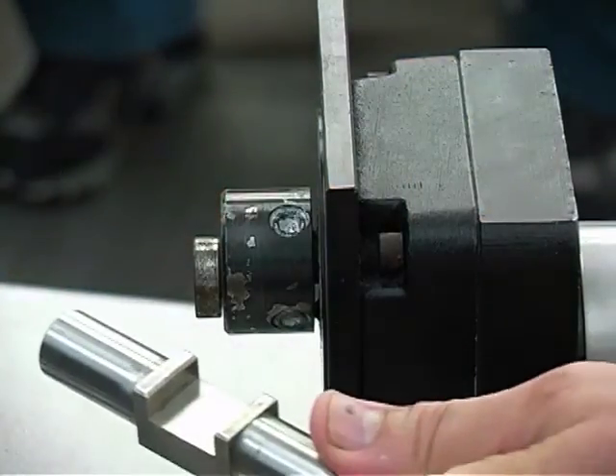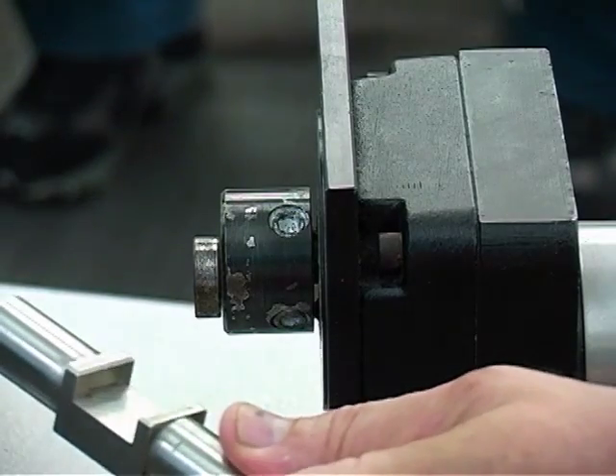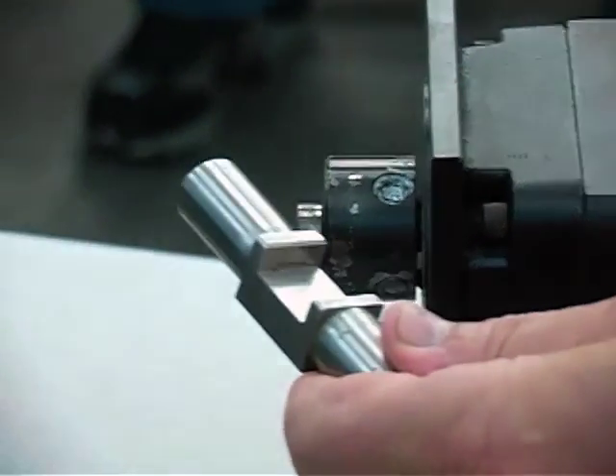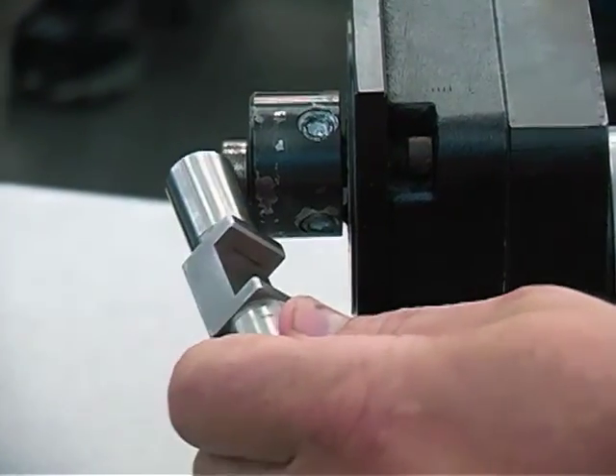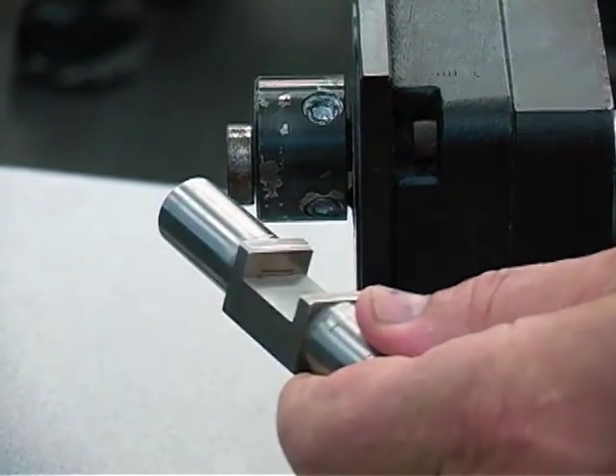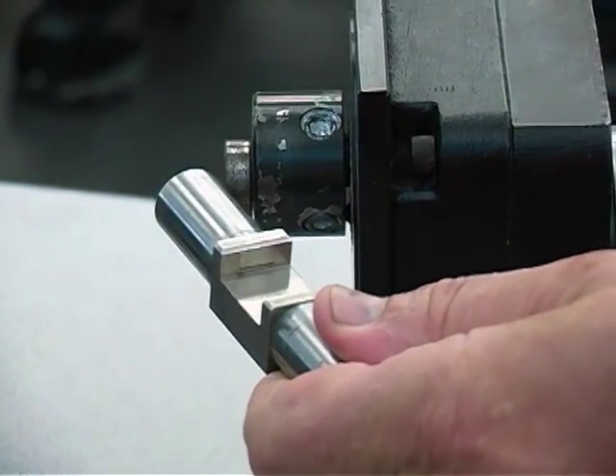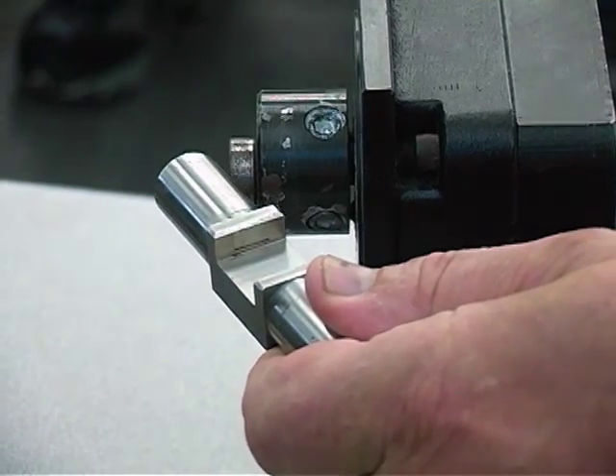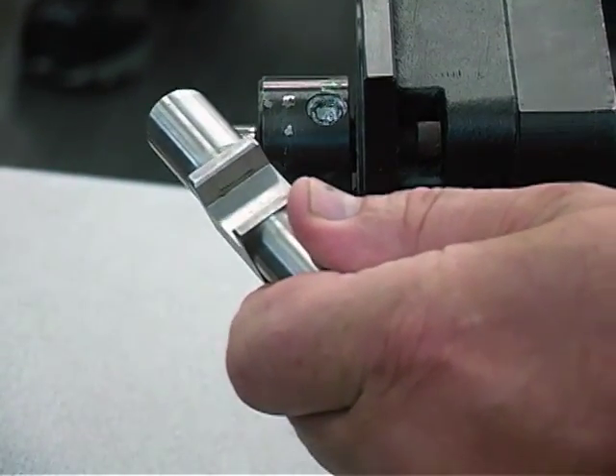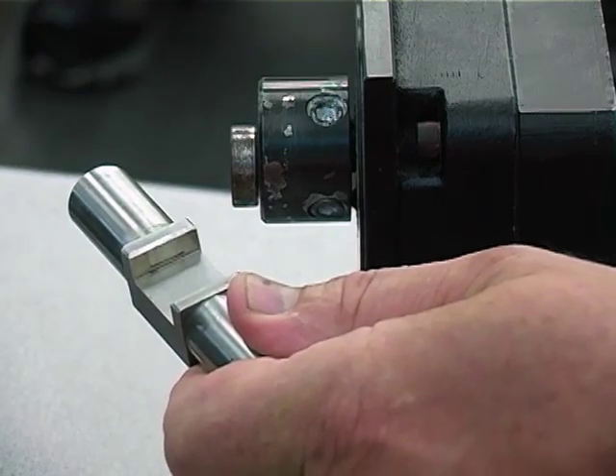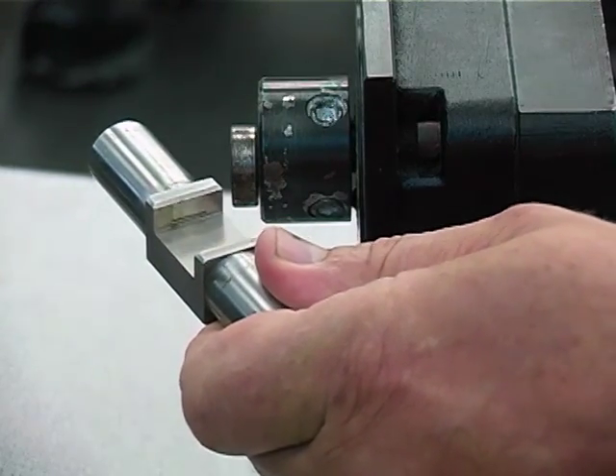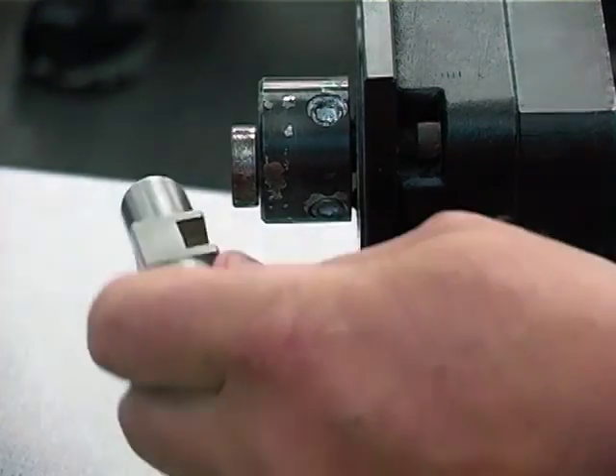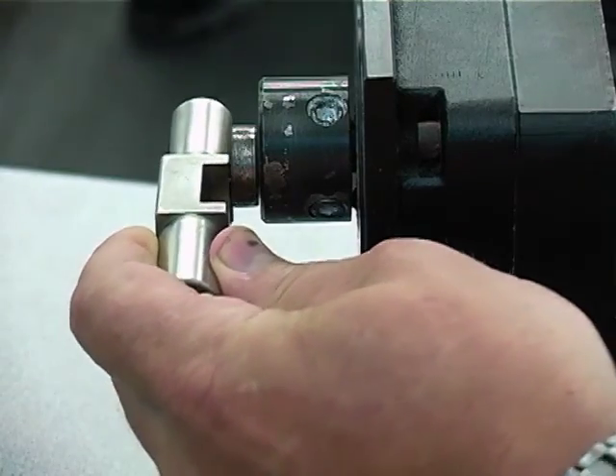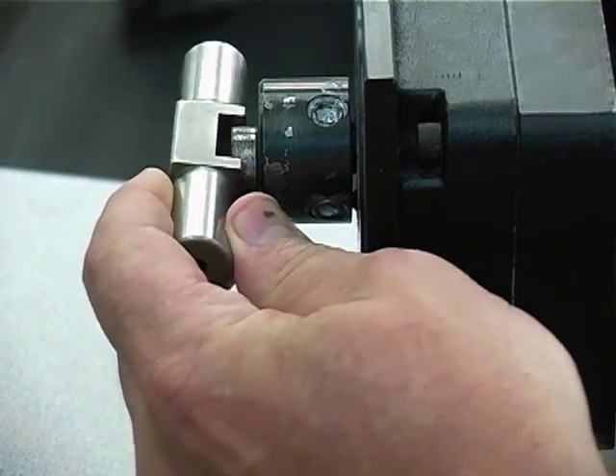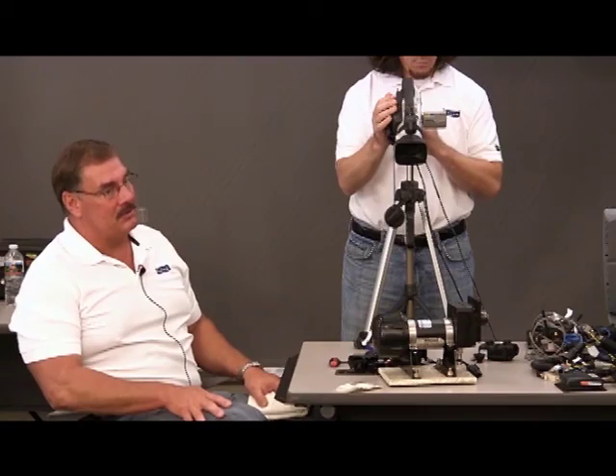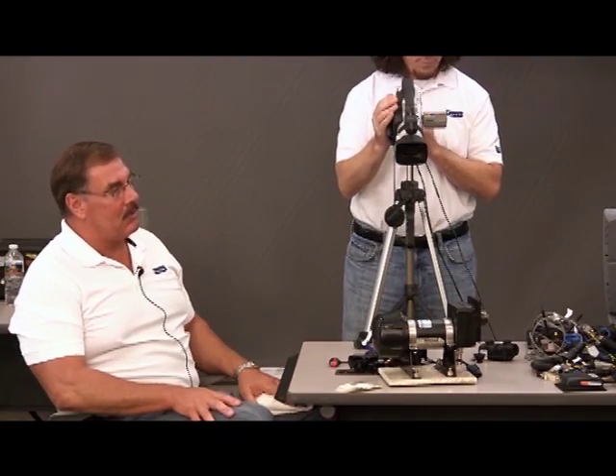The other thing people ask is, do we lubricate things? We've got the little indent here where the bearing sits. Put a little grease in there. I used to say, fill that up with grease. And our engineer said, you do that, you're going to get grease flying out of your weep hole. That's way too much. Put a small dollop of it, and you can use lithium 2 grease, just regular grease, no big deal. You set it on top of the bearing here, and that'll lubricate things up. It's not that hard, it's just, like I said, take your time, go through it.